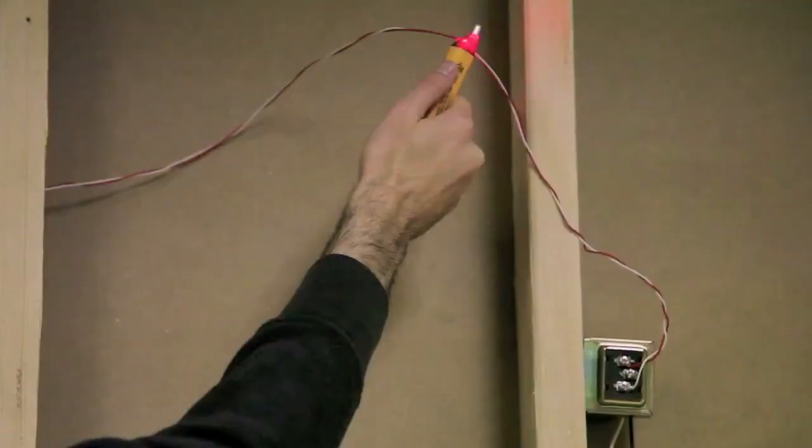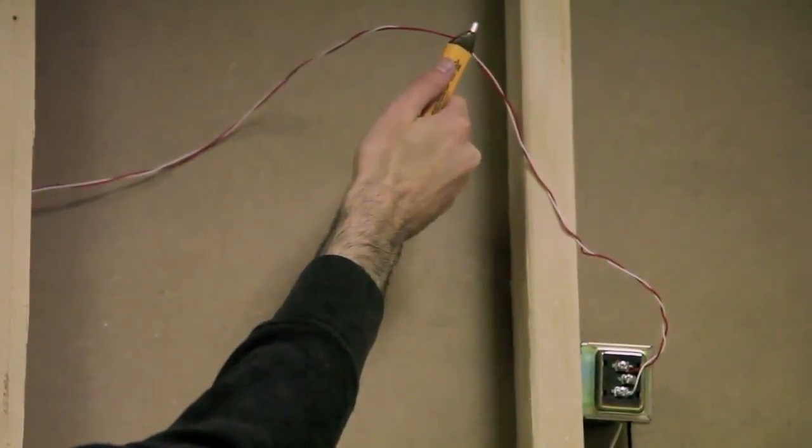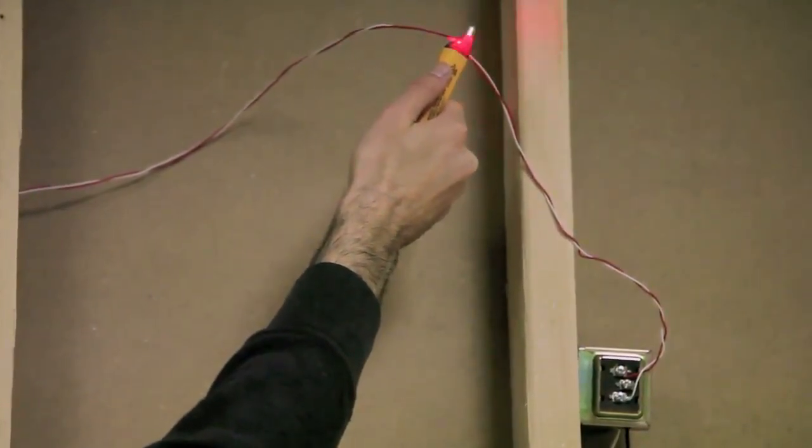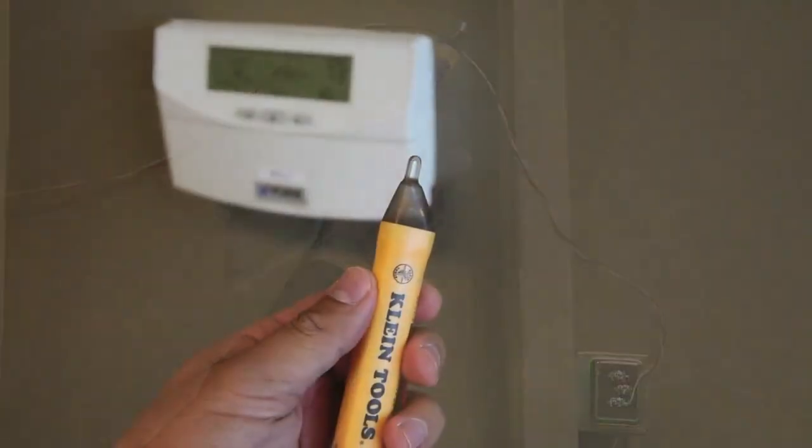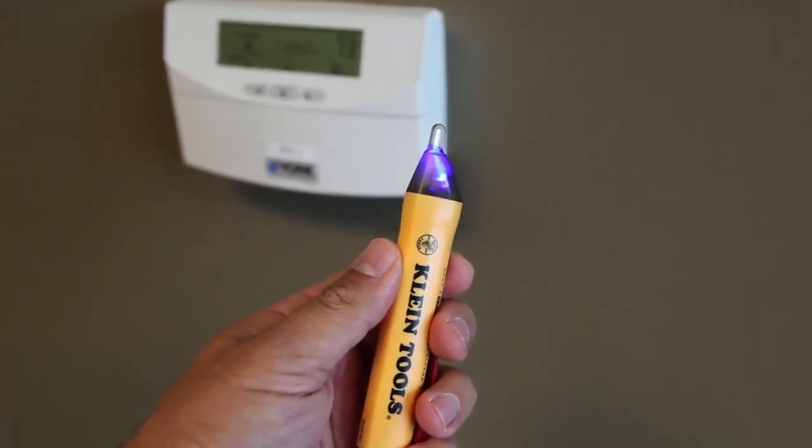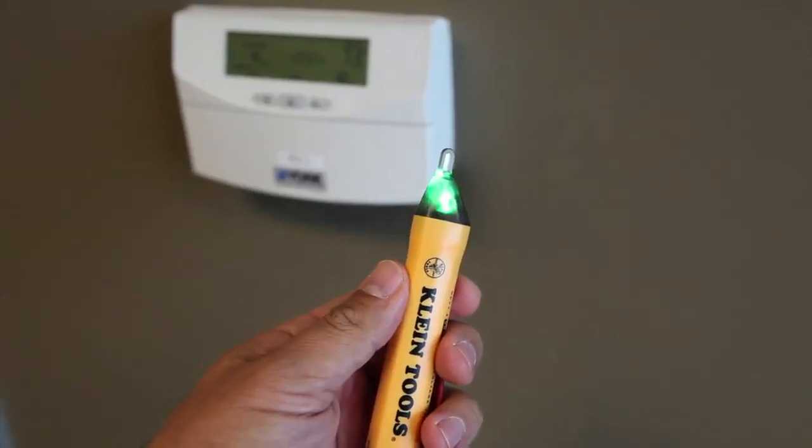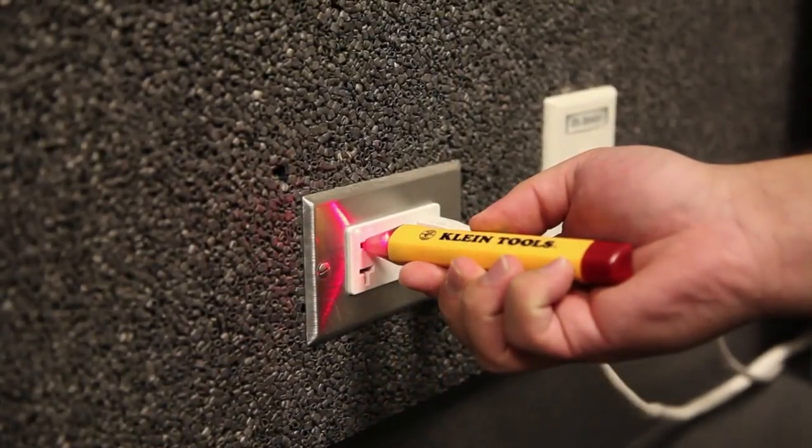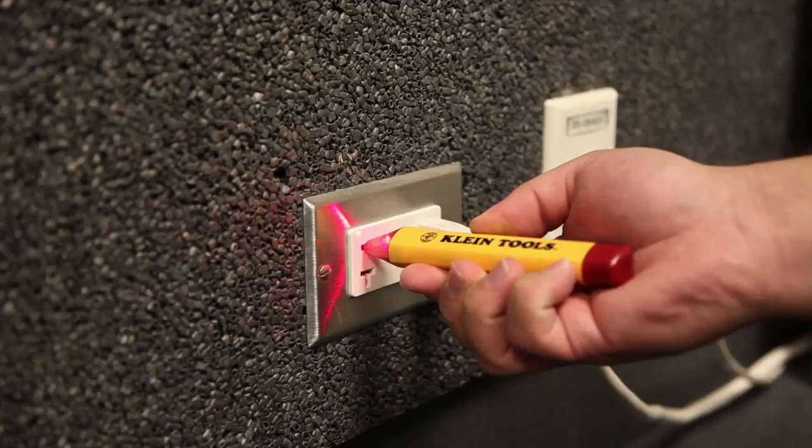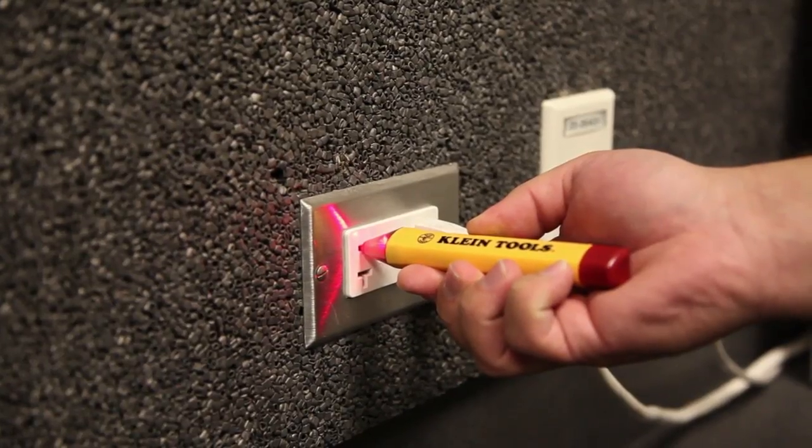The NCVT2 can be switched into NCVT1 mode, which detects standard voltage only. After powering the unit on, press and hold the power button until the blue LED light turns to green. The NCVT2 will produce a low pitched beeping tone and steady red LED light when standard voltage is detected.